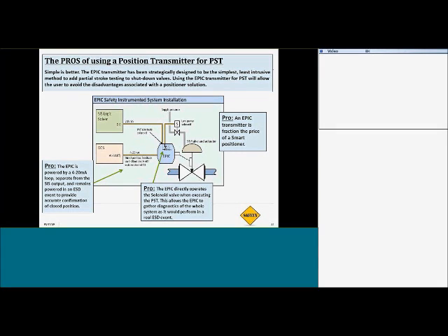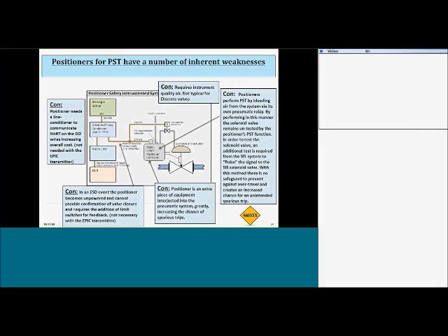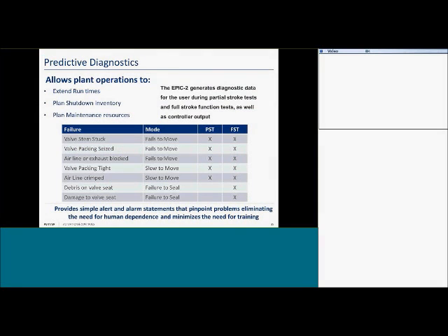And if you have responsibility for this product, I would encourage you to get some additional training specifically on this product, because it's a great area that we can go in and talk with our customers about reducing spurious trips, adding more diagnostics coverage. You can see here, this is some of the pros of using a position transmitter. We actually use the solenoid valve for the test. That's a big, big advantage. While we're in partial stroke test, if there's an emergency, this emergency shutdown valve is still available. It is not available typically in the positioner scheme. So several advantages to using this device, and just one of the ways that we can help our customers optimize the system.